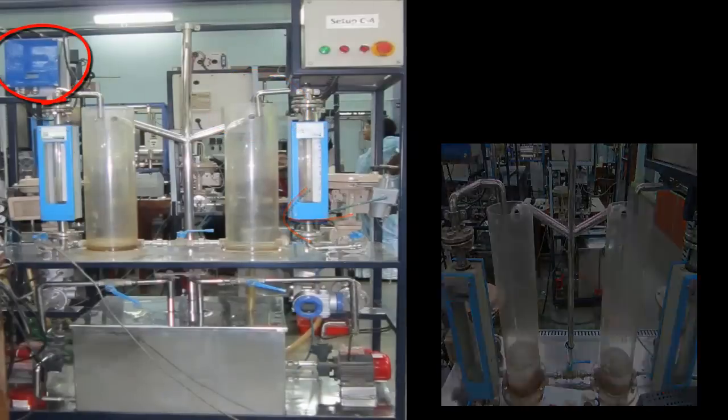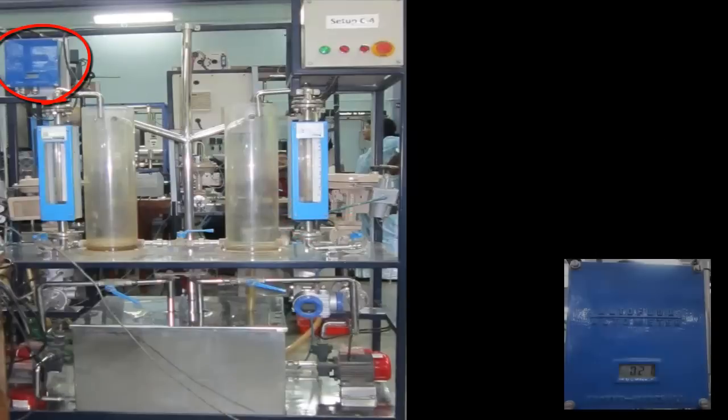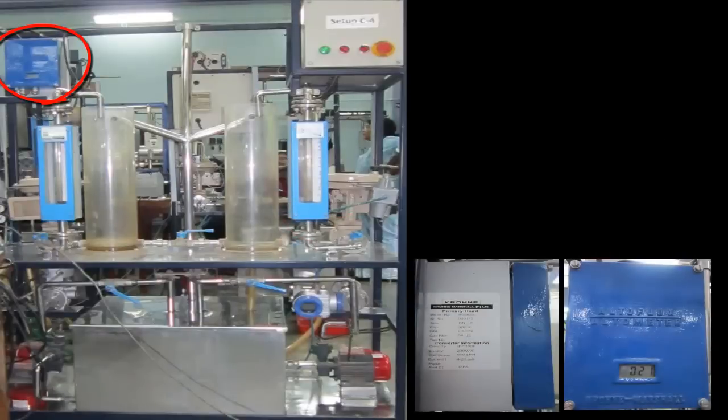On the top left hand corner is the Krohne IFC 4000 electromagnetic flow meter. Electromagnetic flow meters are the third most common flow meters behind differential pressure and positive displacement flow meters. A magnetic field is applied to the metering tube which results in a potential difference proportional to the flow velocity perpendicular to the flux lines. The physical principle at work is electromagnetic induction.